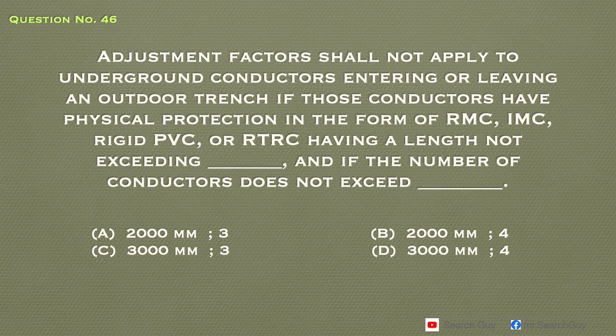Question number 46. Adjustment factors shall not apply to underground conductors entering or leaving an outdoor trench if those conductors have physical protection in the form of RMC, IMC, rigid PVC, or RTRC, having a length not exceeding blank, and if the number of conductors does not exceed blank. A. 2000 mm, 3, B. 2000 mm, 4, C. 3000 mm, 3, D. 3000 mm, 4. Answer: D. 3000 mm, 4.